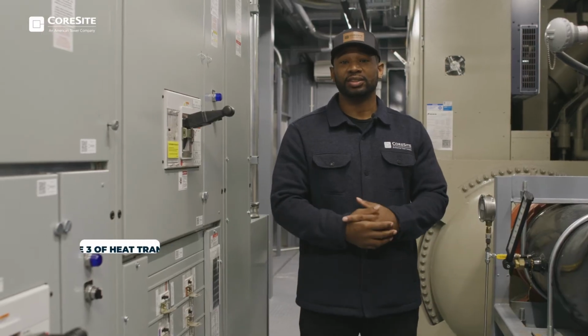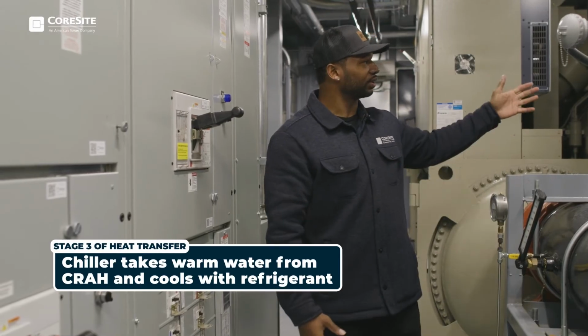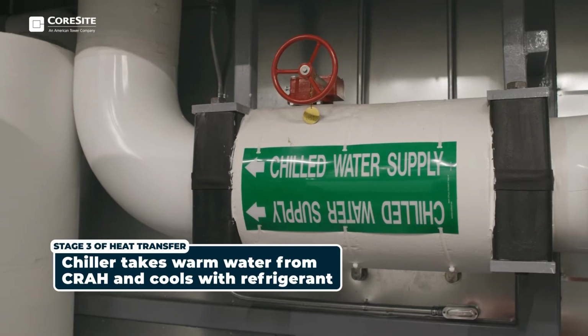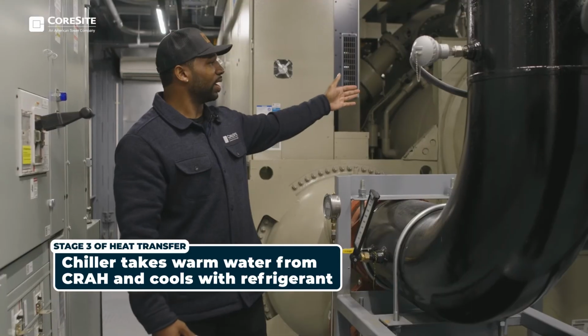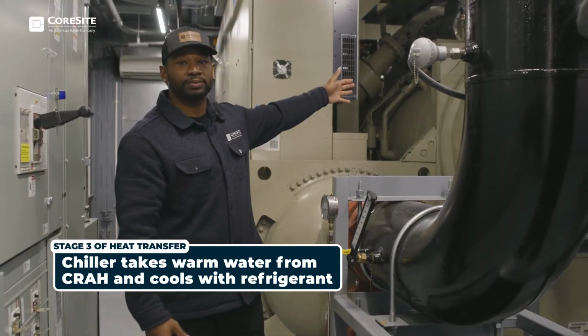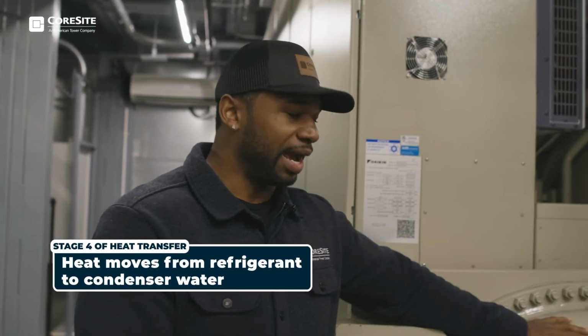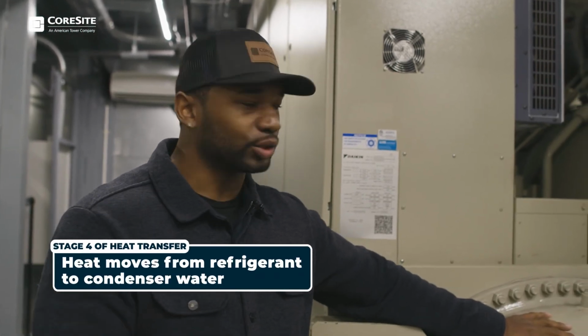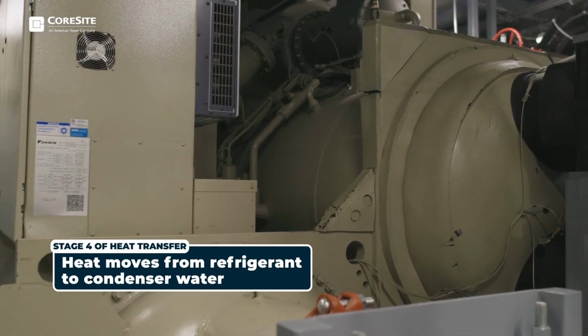The next two stages of heat transfer take place right here at the chiller. That warm chilled water returning from the CRAH units is cooled by refrigerant right here in this tube. The next stage of heat transfer happens right here in the condenser, where heat is transferred from the refrigerant to condenser water.